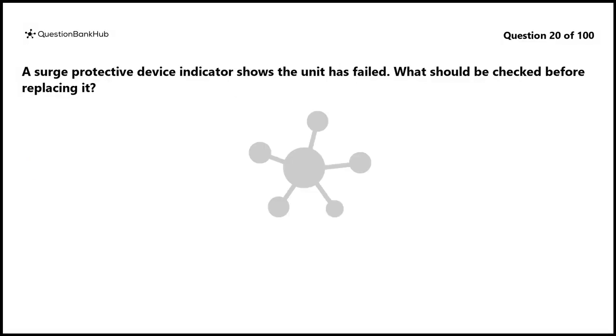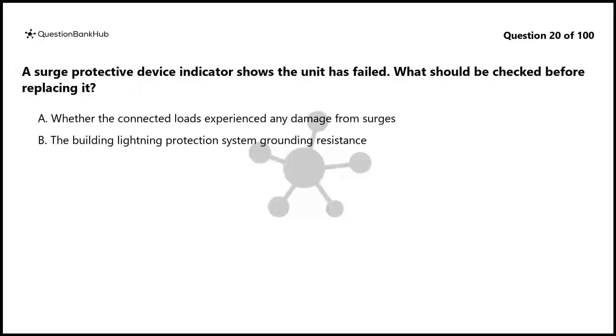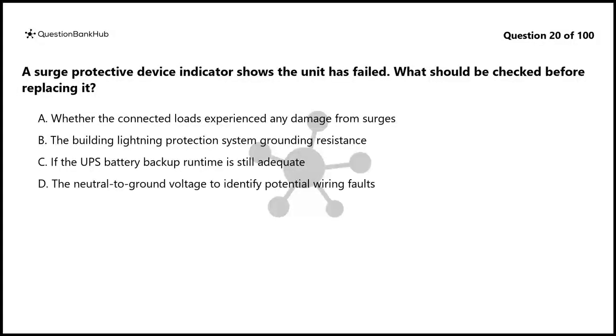Question 20. A surge protective device indicator shows the unit has failed. What should be checked before replacing it? A. Whether the connected loads experienced any damage from surges. B. The building lightning protection system grounding resistance. C. If the UPS battery backup runtime is still adequate. D. The neutral to ground voltage to identify potential wiring faults.